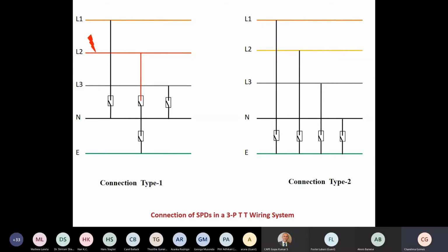Now imagine that lightning strikes line 2, then its potential goes up so that SPD goes into low impedance mode. Now the neutral is at one potential, so all the other SPDs are now subjected to a difference in potential. So they will operate and the whole system becomes single potential. So there will be no potential difference.